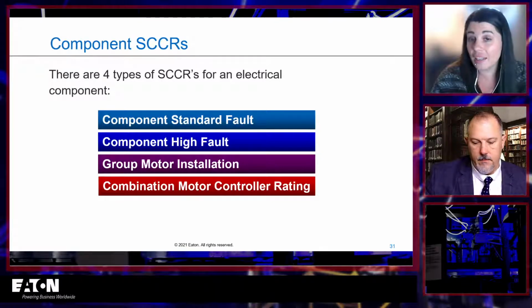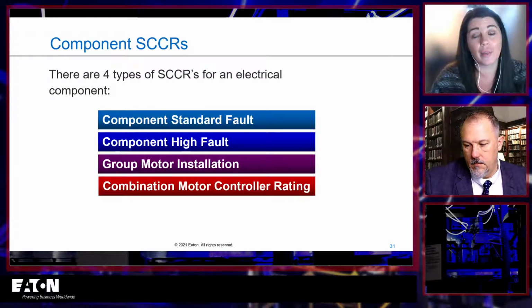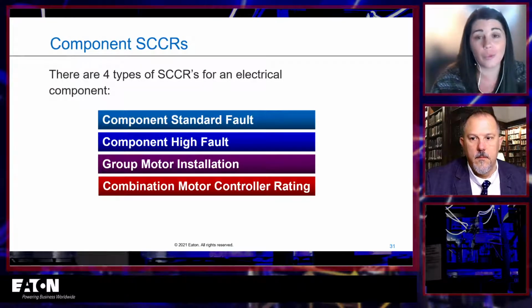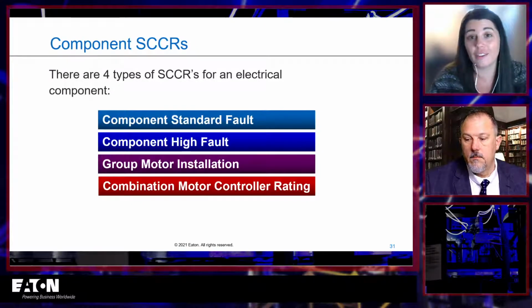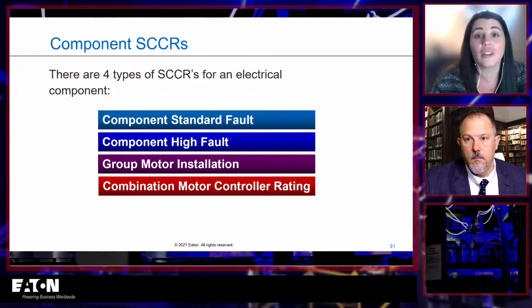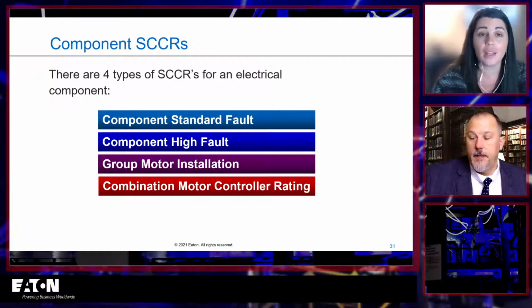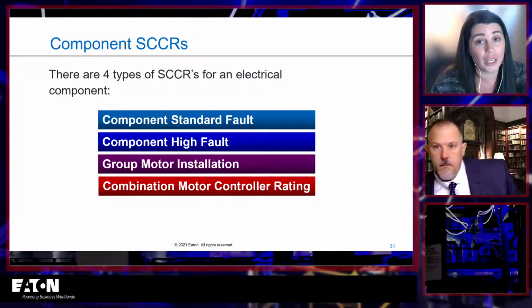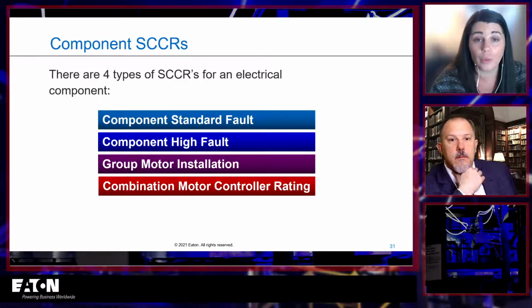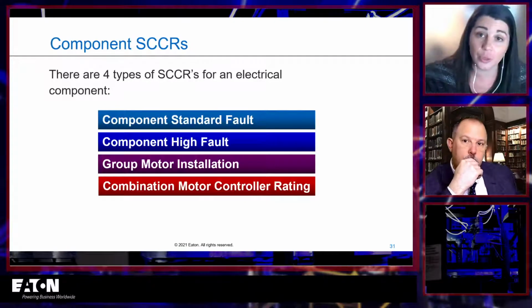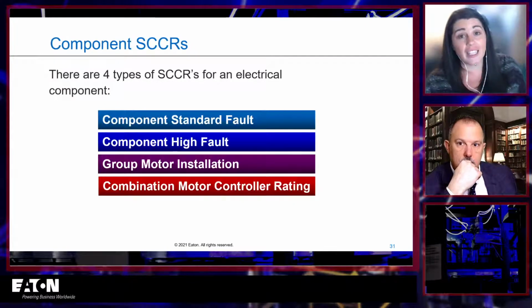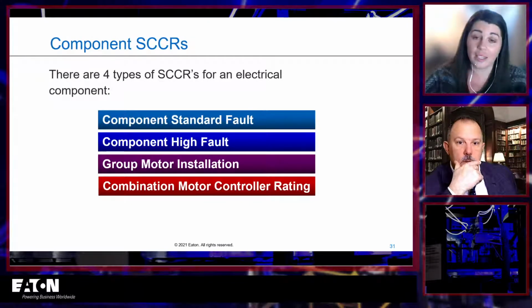Anything that goes inside an electrical panel, more or less, there's a couple pieces of equipment, mostly like line reactors and transformers, that don't have short circuit current ratings, but everything else pretty much has one. That includes the receptacle on the outside of your panel, GFCI or not, contactors, power distribution blocks, non-fusible switches, all of these have a short circuit current rating if they're in the path to a load. And that standard fault level is pretty low for a lot of them. So you want to be aware of what that is. And then more importantly, if you're trying to get a higher short circuit current rating for your panel, you want to investigate some of these other types of ratings to get them higher.